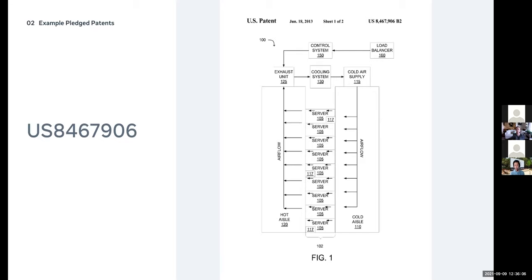That helps us manage the exhaust. You can see the exhaust units and supply units here, which are active fans pushing air through. Given those constraints, a load balancer looks at those dimensions and decides it can send a certain amount of load to a rack because there's still enough pressure differential to cool those servers, while deciding to decrease load in other racks and redistribute it across the data center.